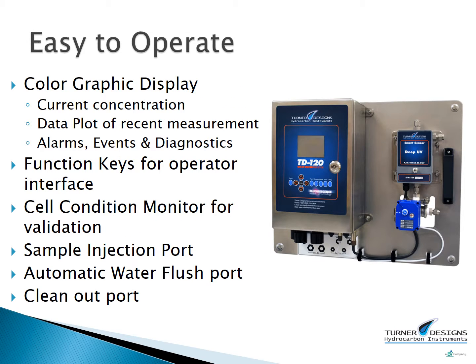Local operators will find that the TD120's display and function keys are easy to use to see the current concentration, a data plot of recent measurements, as well as all alarms, events, and diagnostics. The cell condition monitor included with the TD120 can be used to indicate if the flow cell is clean or dirty. The sample injection point allows a validation solution to be inserted into the instrument as well.